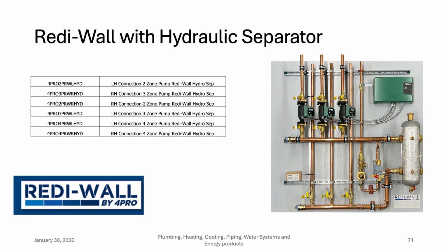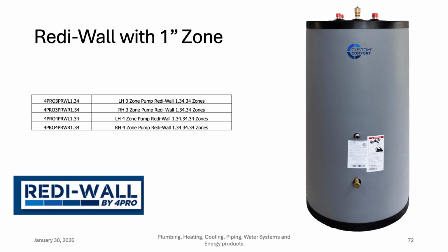We've also got it available with a 1-inch zone. So if you wanted to pipe up a custom comfort indirect off a Redi-Wall, we've got 3 and 4 zone Ready Walls available with a 1-inch zone, followed by either 2 or 3 3/4 zones. So again, a left or right hand connection is available there with a 1 by 3/4 zone header.